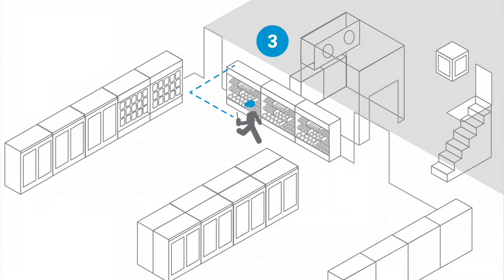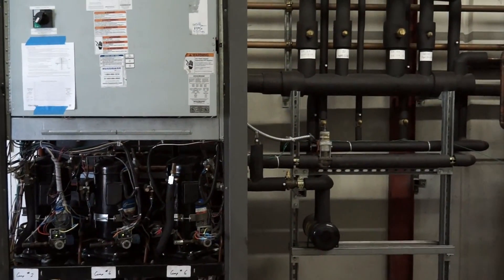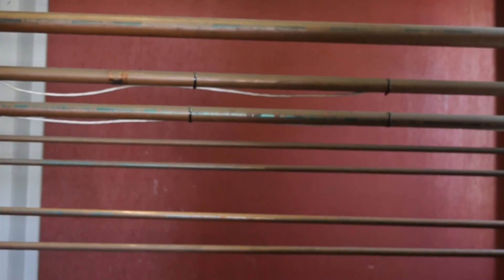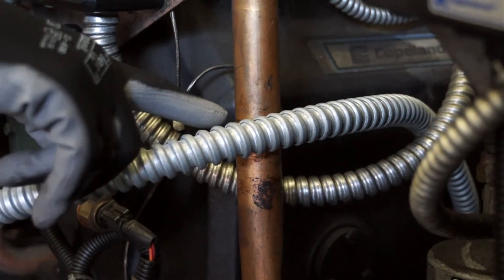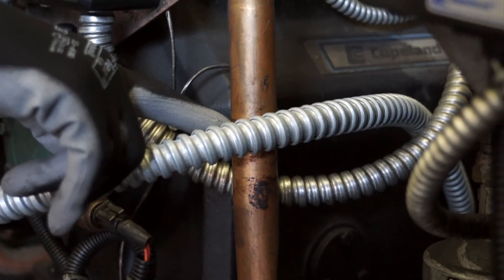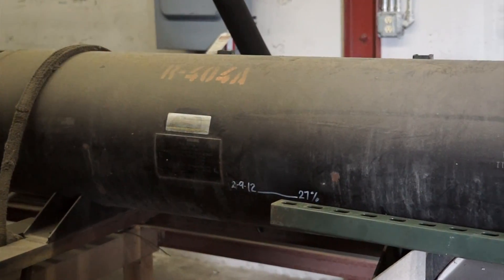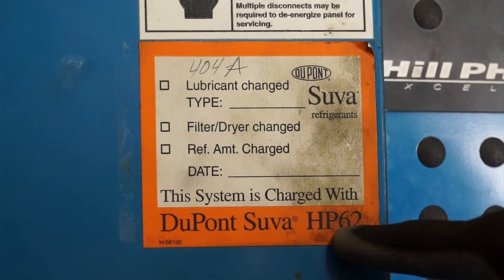Proceed to the machine room. Walk around the equipment and check for obvious problems, oil traces or stains, and unsecured piping or rub outs. Check and mark receiver levels as well as the time and date. Verify the type of refrigerants in each system being checked, and verify exhaust fans work and can be switched off.